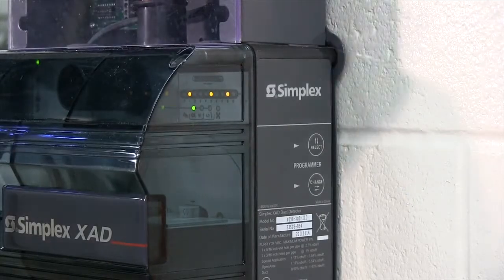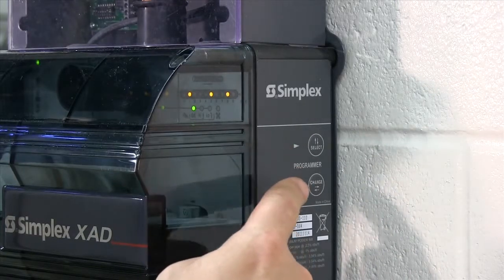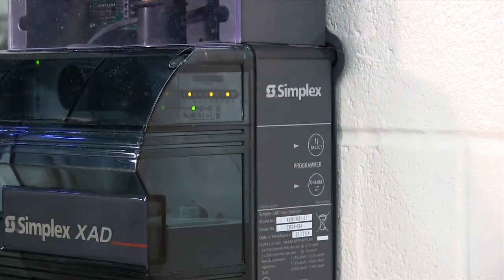Everything can be done at the XAD itself by using these buttons on the side without the need for special tools or programming units. The airflow thresholds and sensitivity settings must be carefully selected based on the application. Improper settings may result in an unnecessary airflow trouble.